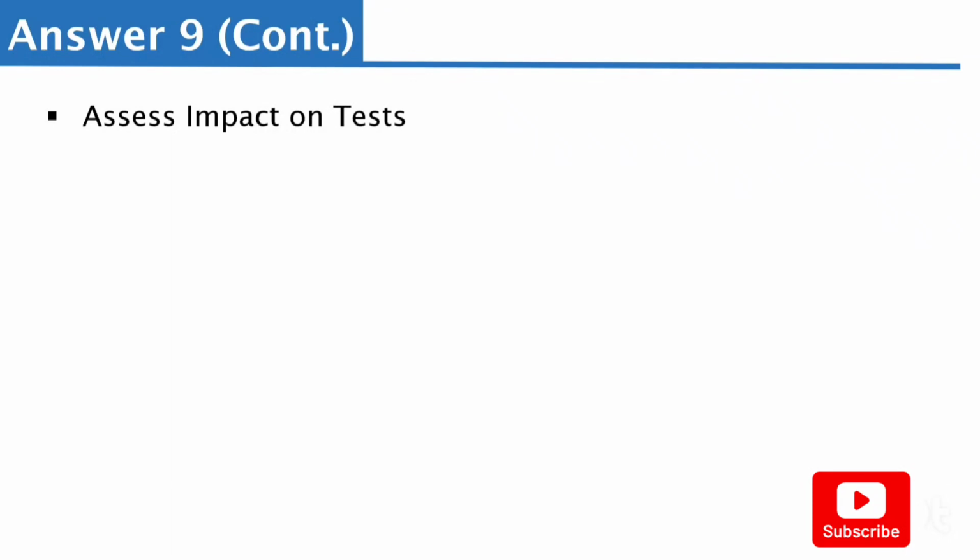So you assess the impact it's going to have on the test, meaning the samples that have already gone through that very analyzer. Now, you are going to communicate with the stakeholders, maybe things like the A&E, or the doctors, or the different wards. In any way you can, communicate to show that the laboratory is down, the equipment is down. It is important that the doctors know that the laboratory is down. That will help them to see how they can manage the patient, okay, while waiting for the laboratory to come up and running. I hope that makes sense. And this is also important because they may now need to start sending only the urgent samples.